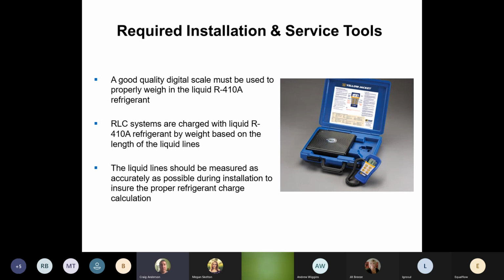Modulating compressors, mini splits, the higher end 5-stage air conditioner, you can't check pressures with your gauges because we have no idea what stage the compressor's in or the EE valve that's monitoring the refrigeration going into the system. Your gauges aren't telling you because we have no idea what stage that unit is. So really we have no idea what pressures we should be reading at that point. So the only way to do it properly is to weigh the gas in.